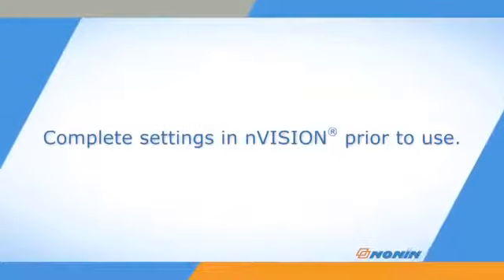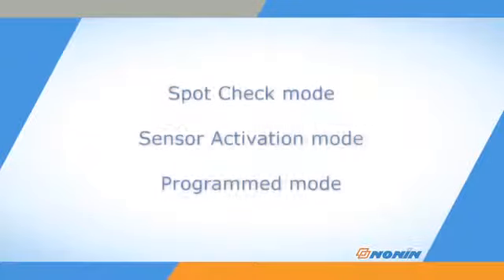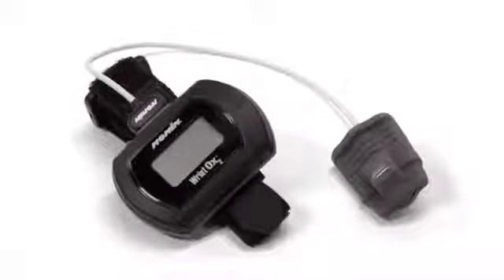Settings and startup modes should already be completed, programmed on the WristOx2 before putting it in use. The oximeter can function in 3 start modes: spot check mode, sensor activation mode, and programmed mode. Verify the startup mode your pulse oximeter is using prior to use. Once batteries are installed in the oximeter, it is automatically in standby mode, ready for use. The screen will remain blank until the oximeter is started in one of its startup modes.